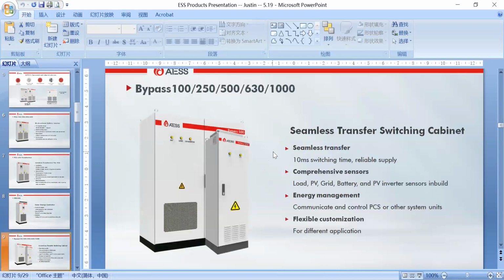Okay, next one, bypass, is another accessory of our PCS. Okay, bypass, the full name is seamless transfer switching cabinet. Okay, and we have bypass 100, bypass 250, bypass 500, bypass 630, and bypass 1000. Okay, we call it seamless because all the transfer switching time is less than 10 milliseconds. Okay, we provide very stable and reliable power. Okay, then what will connect to our bypass? Our load, our grid if we have, our diesel generator, our battery, even our PV inverters, grid tie inverters, because we can seamlessly transfer all the supplies between them. Okay, not only one supply, all the supplies. Depends which one we have powerful.